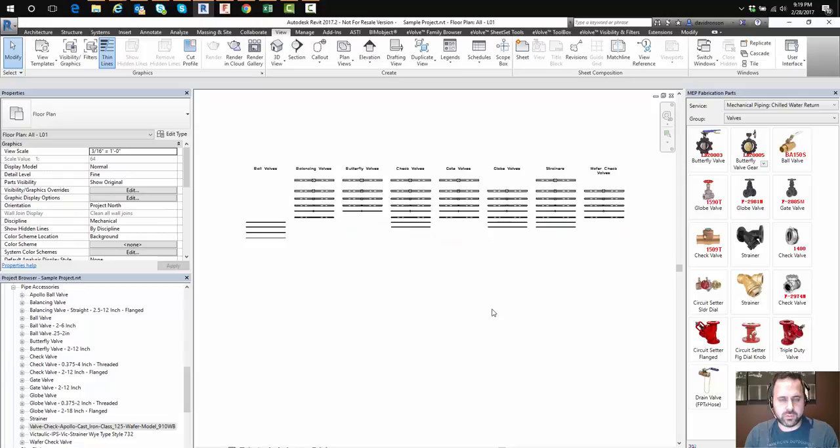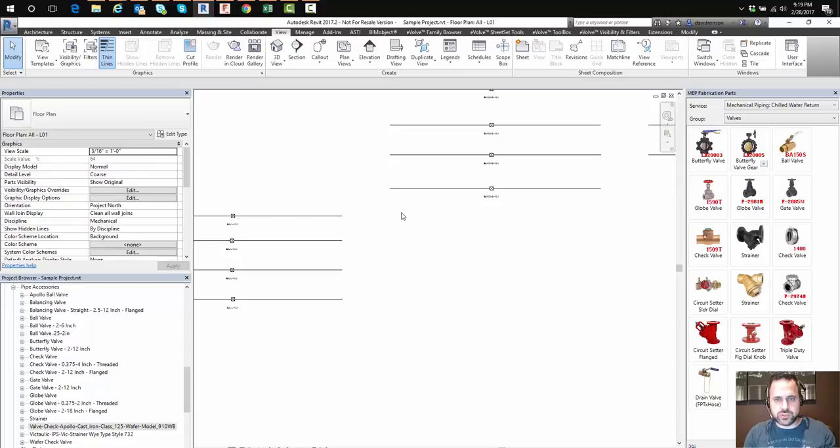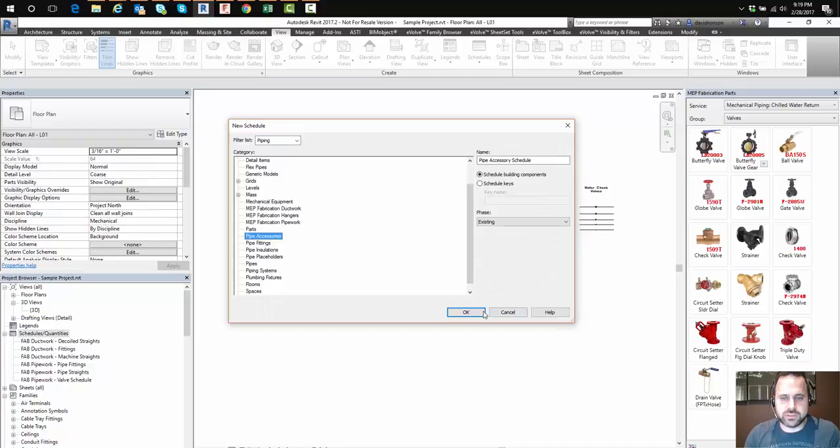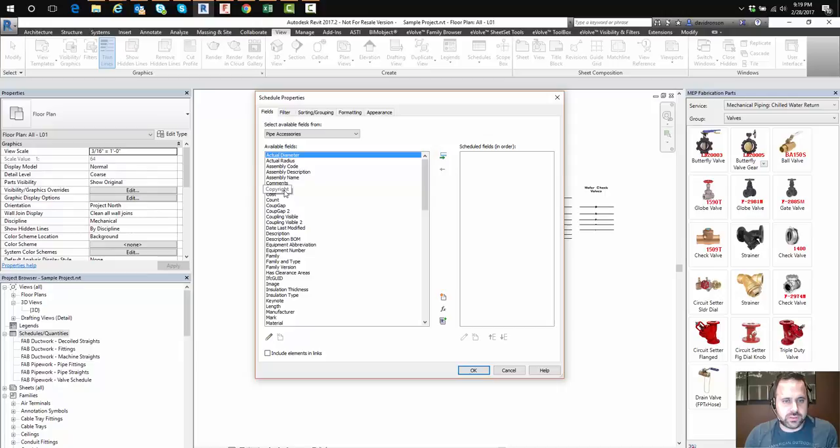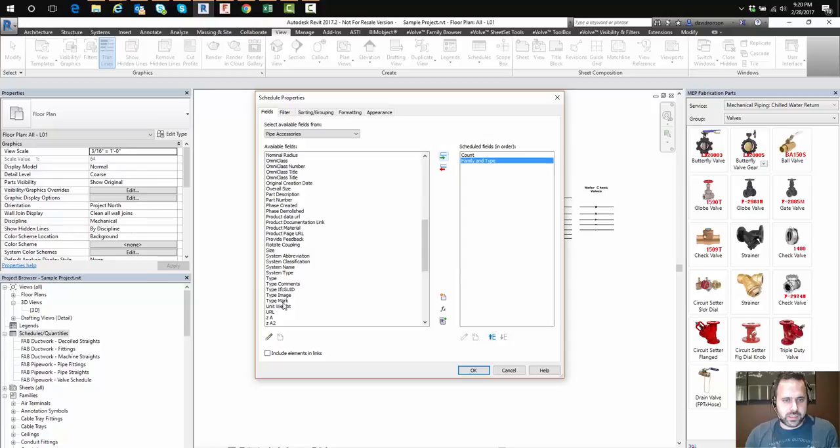Okay, there is another mapping method that we could do. It's not as reliable. One of the great things about Revit is the ability to just swap out families for the same type of family. So I'm going to undo until I get my families back here. All right, so I'm going to go build a schedule of all my pipe accessories. And valves fall under the category of pipe accessories. And I'm still working on figuring out what all else falls under that category. If I go to count, which is equivalent to quantity, I'm going to put in the family and type. That will give me the name. I'm going to put in size. That will tell me the size. And typically I'm not going to itemize every instance.